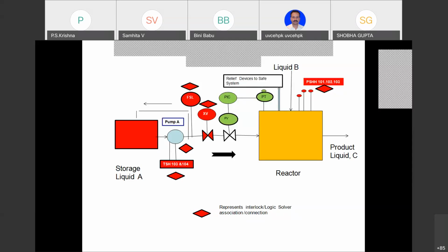Now, having said that, you got 3. Why are you putting 3? Because each switch has its own inclination to work or not work. That is, there is a thing called probability of failure on demand. What is the demand? Everything is at 30 psi, suddenly it goes up to 45, like a flash. When it goes to 45, it is supposed to behave and say, yes, please shut down. It tells the logic controller. So suppose that day, to your bad luck, it does not do so, then a hazard or catastrophic action can take place.